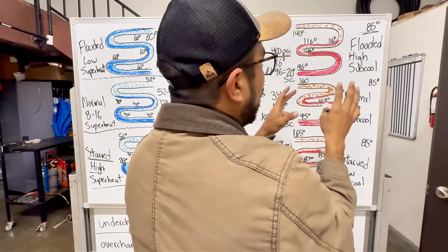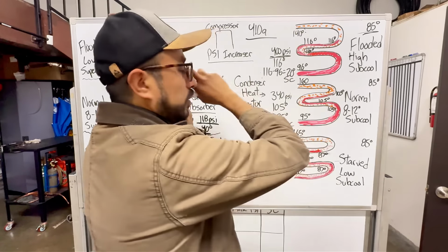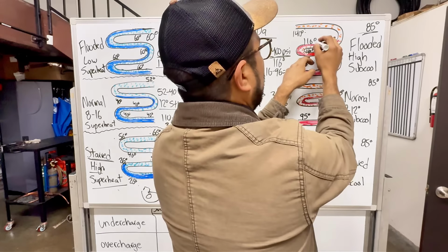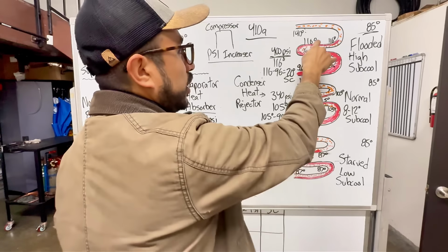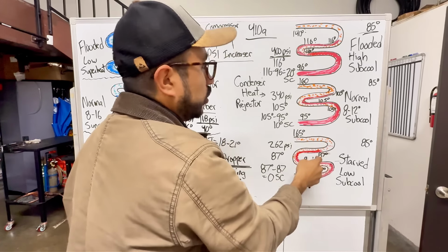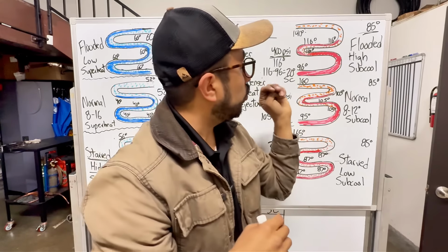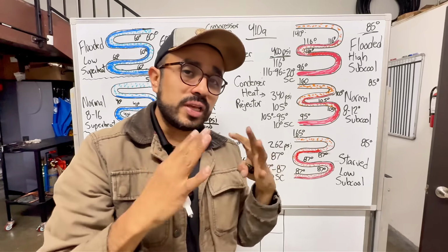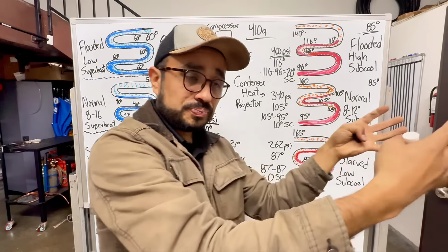So the thing is that with the system that is overcharged, because you have too much refrigerant, and remember, here's the key. Can 116 go into 85? Absolutely. And you're going to see how that varies with the system that's undercharged. 116 to 85, you got about, what is it? 95, 106, about a 30-degree difference. You can definitely reject heat. You can reject a lot of heat.